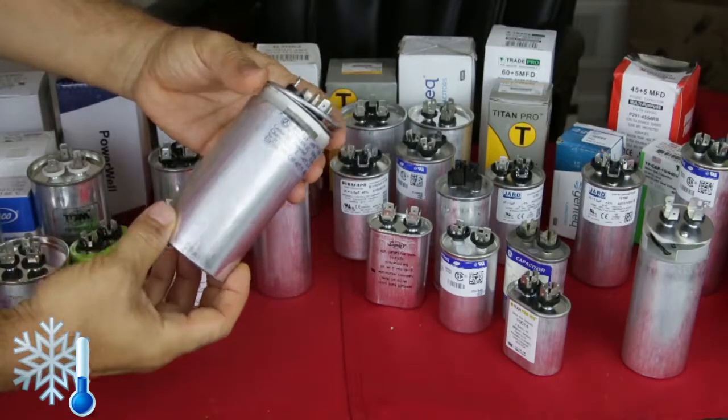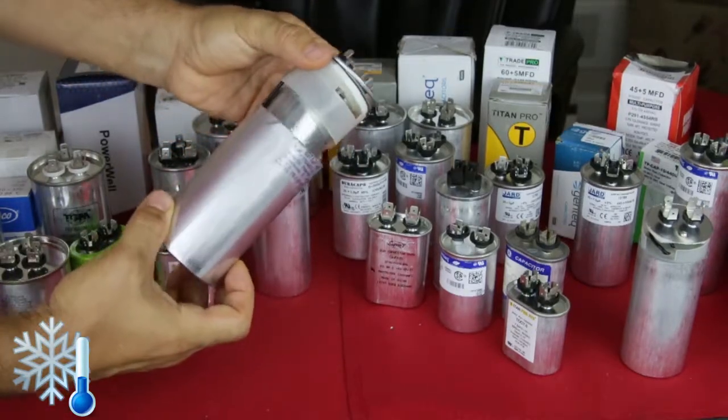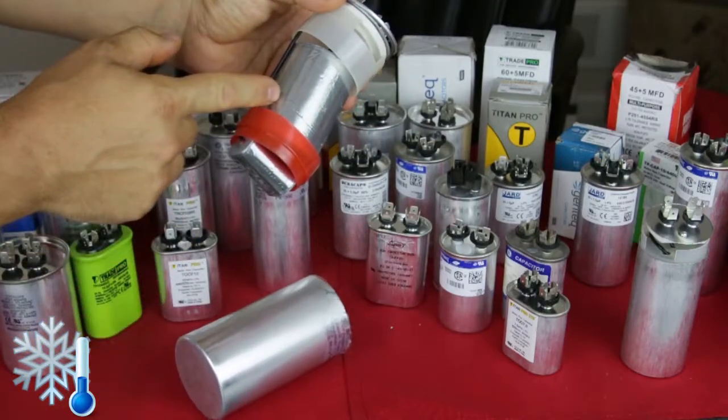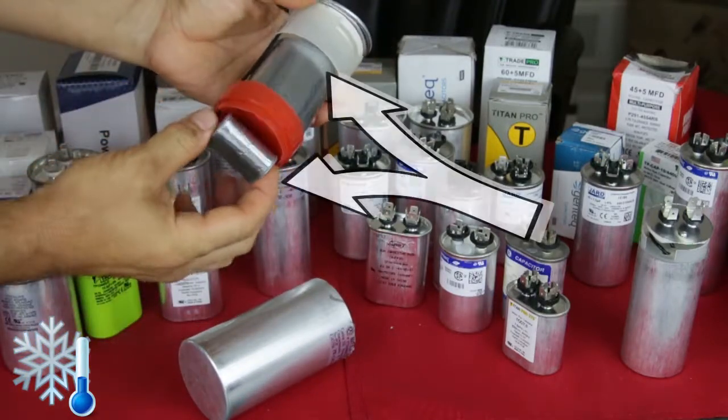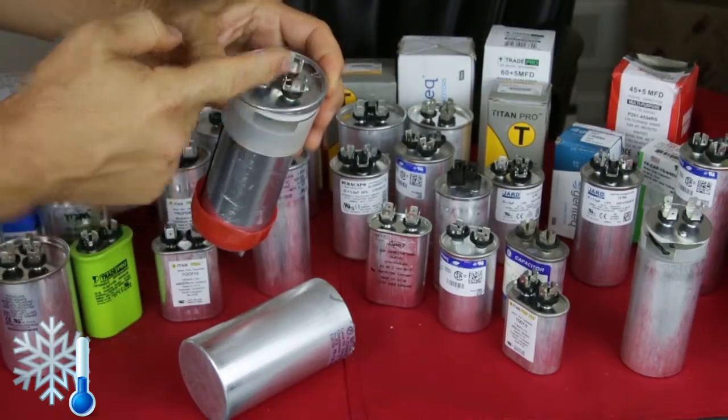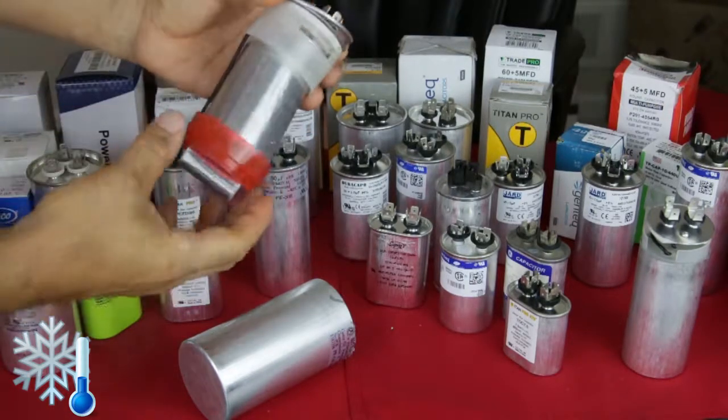In the dual capacitor what we see is the three terminals on top. If you open it we're going to see actually two single capacitors connected. They're going to have the common terminal and each one is going to have the side for the fan or for the compressor.